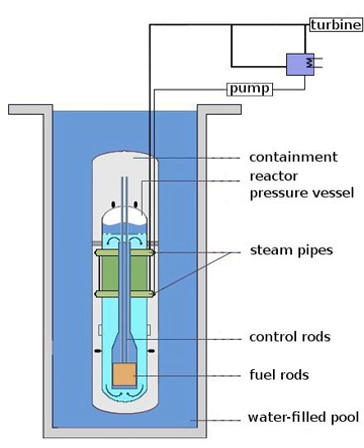The light water reactor produces heat by controlled nuclear fission. The nuclear reactor core is the portion of a nuclear reactor where the nuclear reactions take place; it mainly consists of nuclear fuel and control elements. The pencil-thin nuclear fuel rods, each about 12 feet long, are grouped by the hundreds in bundles called fuel assemblies. Inside each fuel rod, pellets of uranium, or more commonly uranium oxide, are stacked end-to-end. The control elements, called control rods, are filled with pellets of substances like hafnium or cadmium that readily capture neutrons.